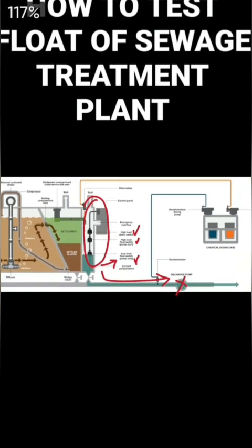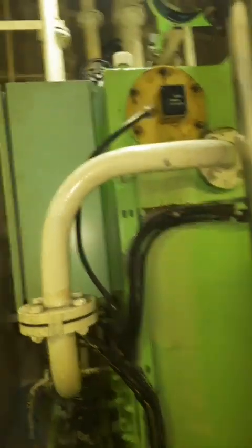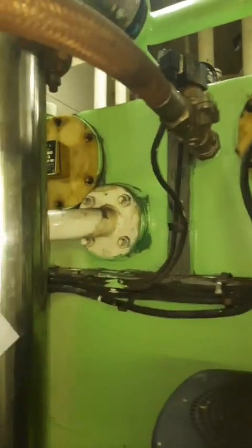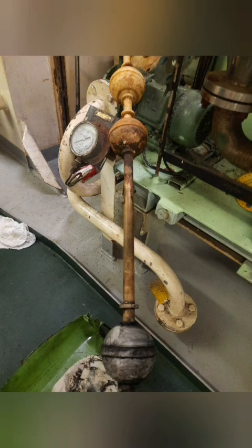This is the basic testing of the sewage treatment plant, which we will discuss in this video on an actual sewage treatment plant. Now you can see here the float switches on this plant, and inside the chambers the last chamber looks like this. The water is filled up in this fashion. This is the float switch which is put inside. We have taken out the float switch — you can see here the three floats.